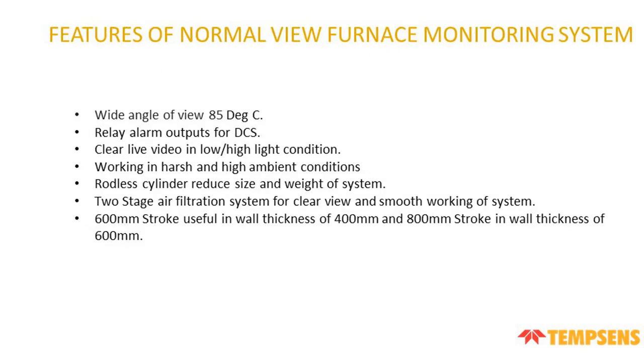Features of the normal view furnace monitoring system: wide angle of view, diagonal 85 degrees, 65 horizontal and 56 degrees vertical. Relay alarm output for DCS. Clear live video in low and high light conditions, working in harsh and high ambient conditions. Rodless cylinders reduce the size and weight of the system. Two-stage air filtration system for a clean view and smooth working of the system.